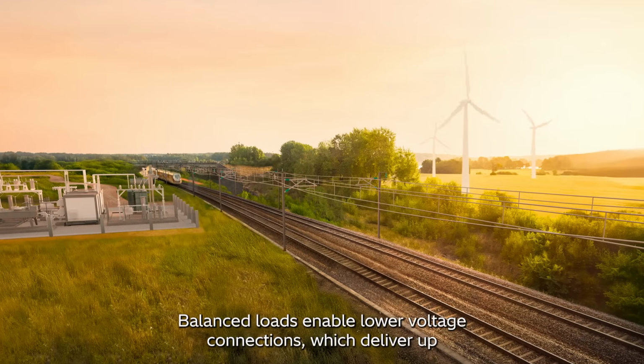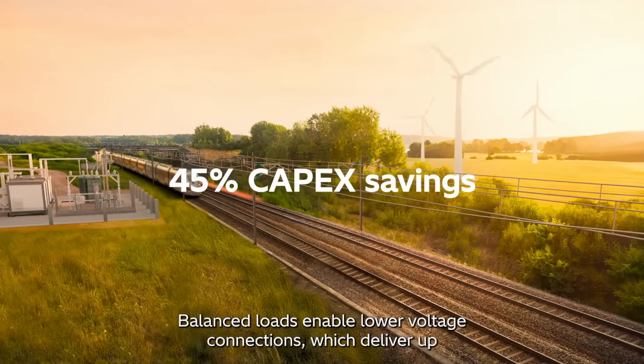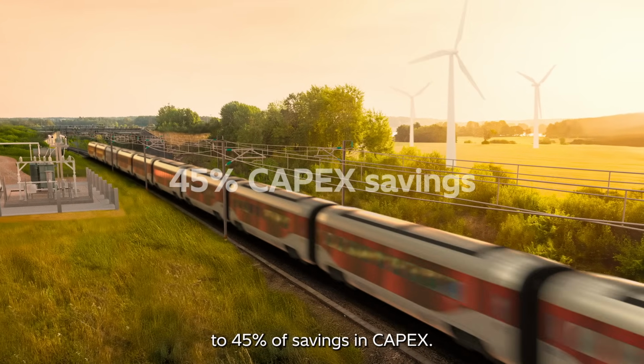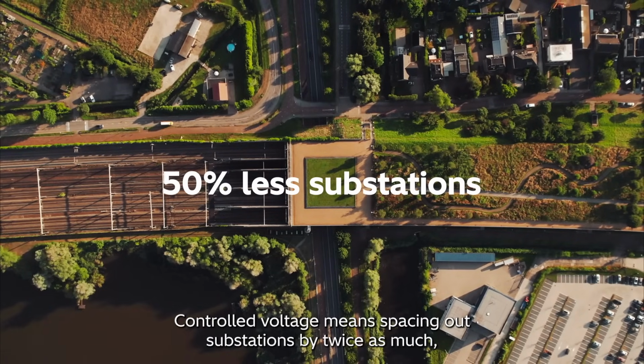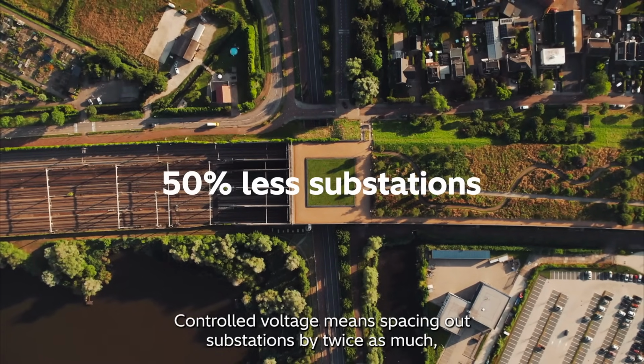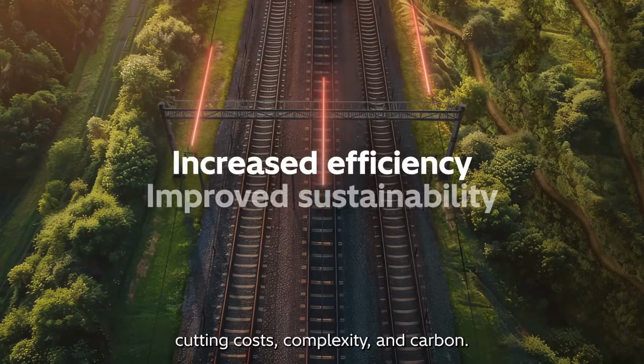Balanced loads enable lower voltage connections, which deliver up to 45% of savings in CAPEX. Controlled voltage means spacing out substations by twice as much, cutting costs, complexity, and carbon.